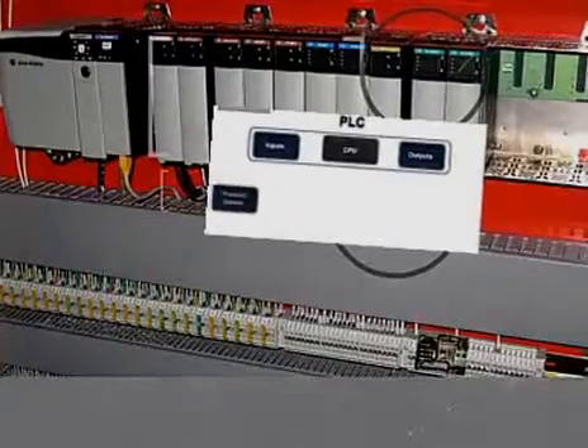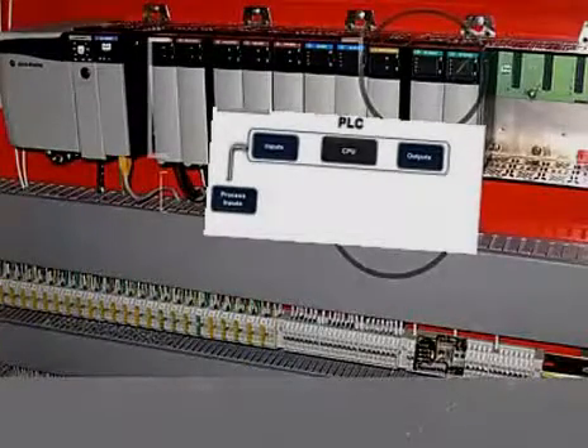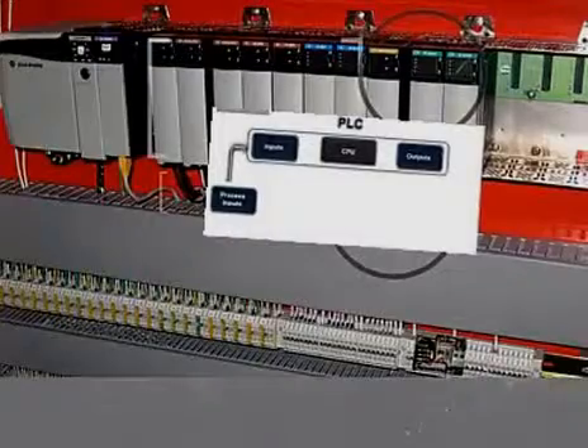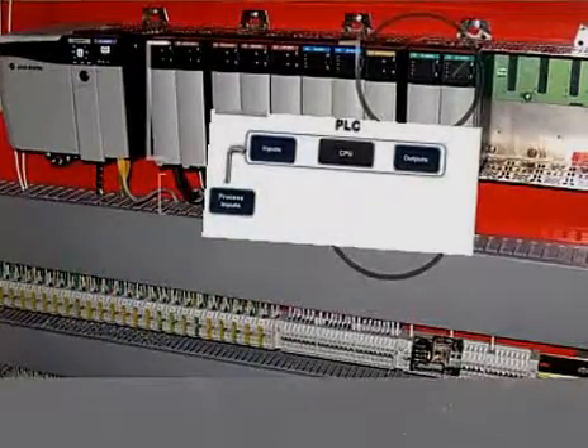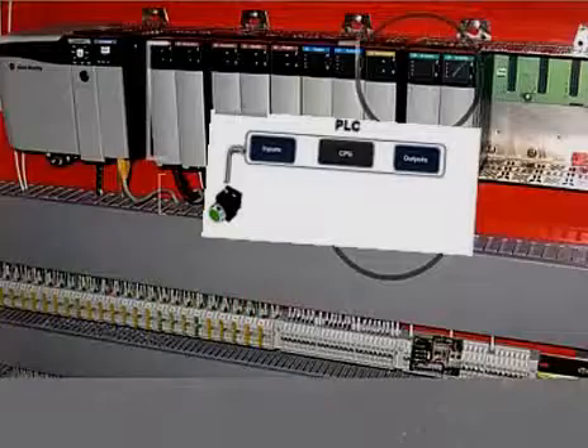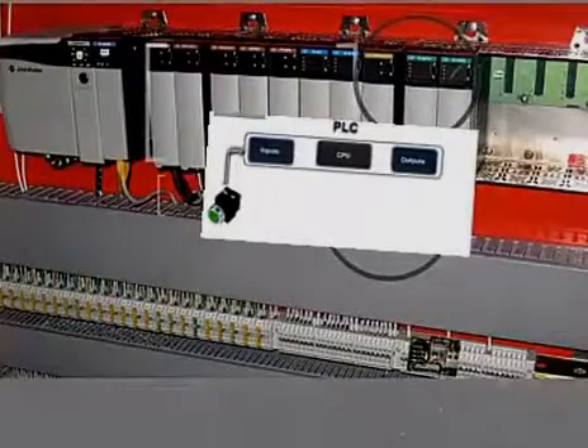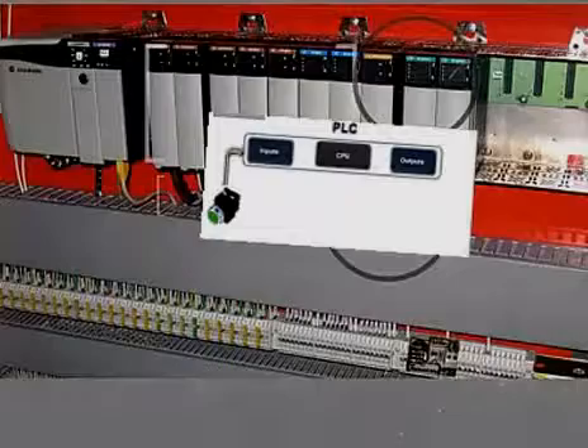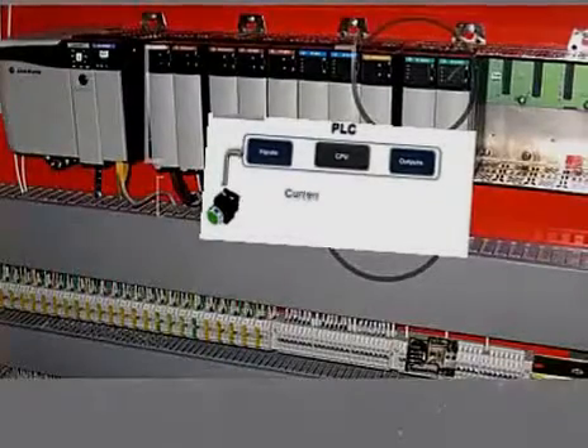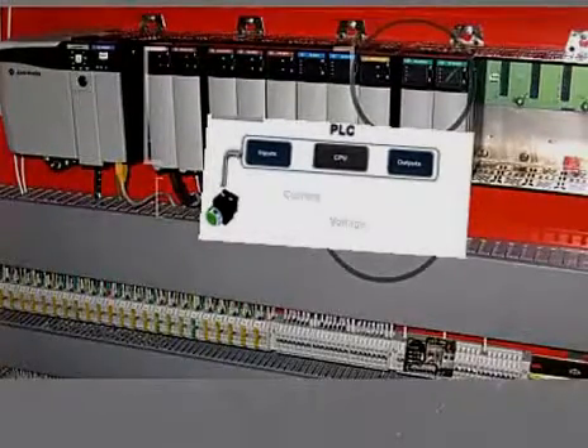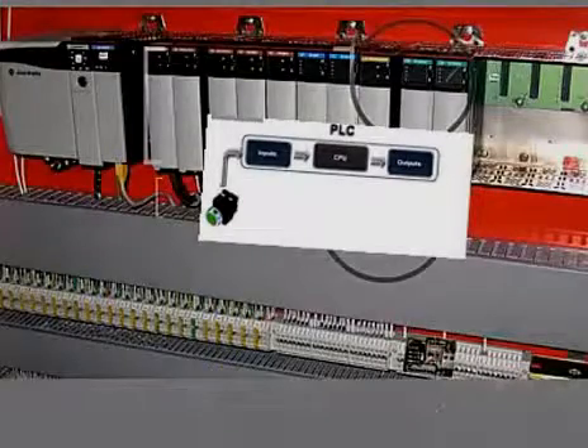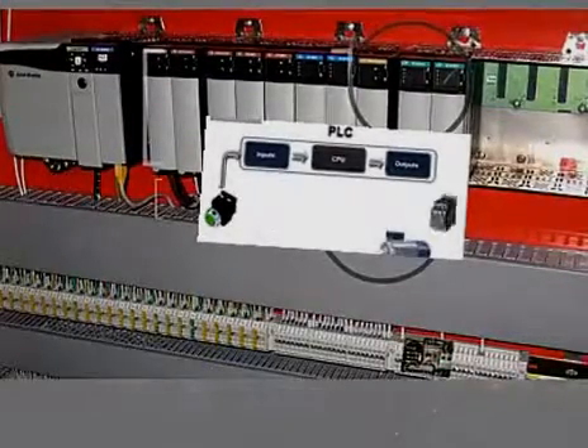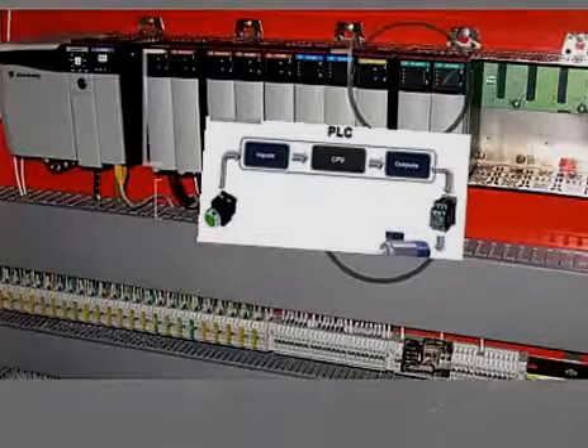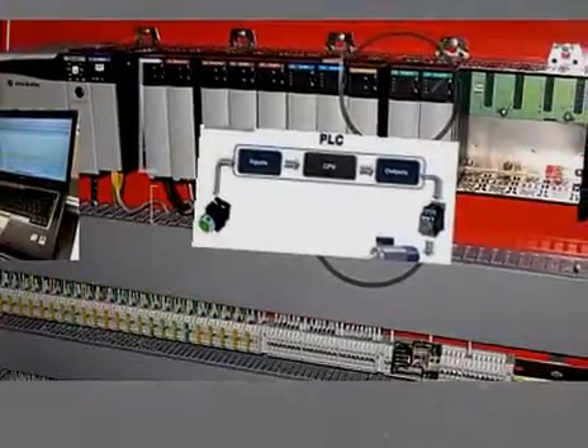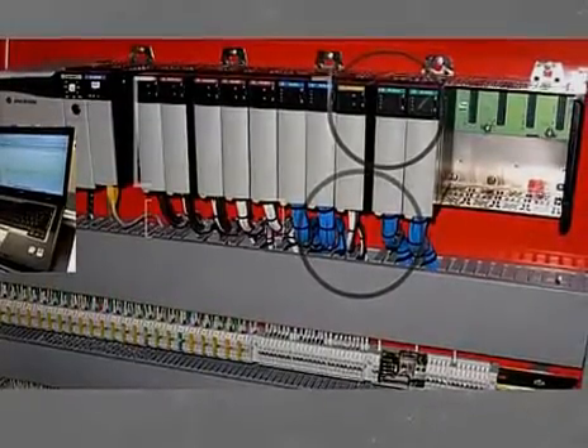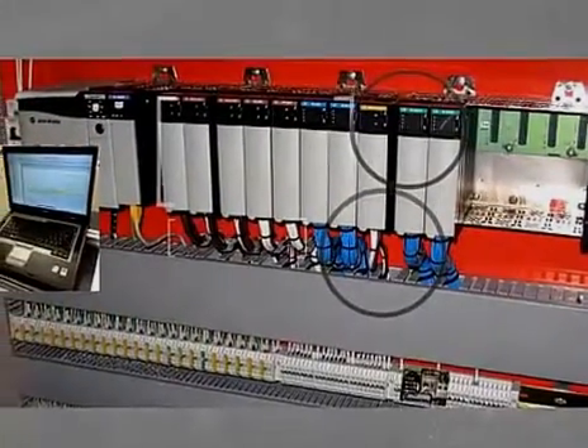The input-output interface is the communication link between field devices and the controllers. Through these interfaces, the processor can sense and measure physical quantities regarding a machine or process, such as proximity, position, motion, level, temperature, pressure, etc. Based on the status sensed, the CPU issues commands to output devices such as valves, motors, alarms, and so on. A programmer unit is used to enter the application program, which often uses a simple, user-friendly logic.